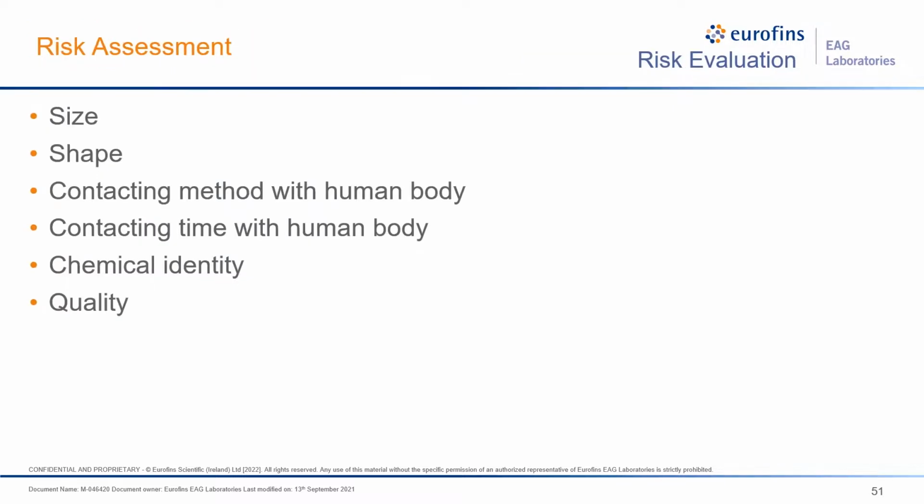Once we have the chemical composition determined, next following is always risk assessment, especially for the industry's potential patient risk is of concern. The size of it, the shape of the particles, especially if the sharp edge that could cut the inner organs, those are all of concern of risk assessment, of course. And the contacting method of human body, is it just dermal contact, or is it embedded or like implanting devices? And also contacting time with human body is also of concern.